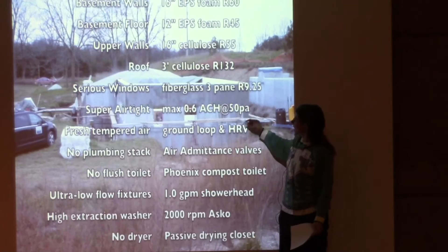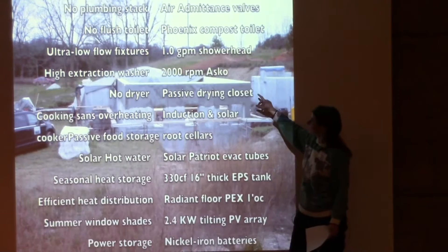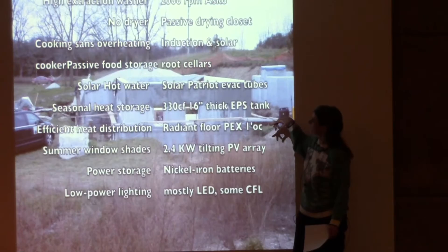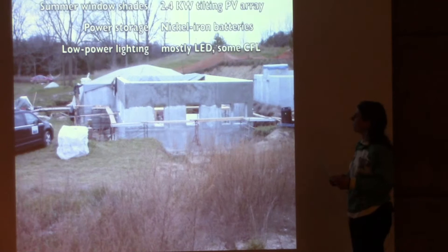The windows are R-9.25. Super airtight at 0.6 air changes per hour. No plumbing stack, no flush toilet — a composting toilet is used. The dryer is actually part of the ventilation system, and solar hot water evacuated tubes will provide seasonal heat storage. We'll also have a solar PV system and LED lighting.